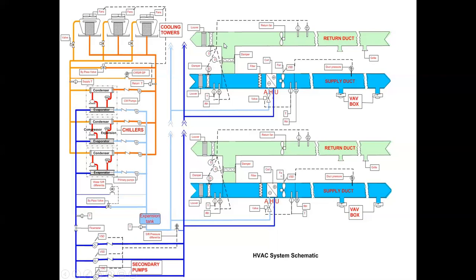When it's 0 degrees outside, ventilation air is expensive because it has to be heated up to 70 degrees. Well, return air, if I'm air conditioning, is going to be what, 78, 80? That outside air might be 95. I don't want any more of that outside air than the ventilation code tells me I have to have. Now with COVID, good Lord, who knows what impact COVID is going to have on all these codes and requirements. But we're going to return air, and then we have the ability to dump some of that air outside with dampers. Generally, though, we would return the majority of it.